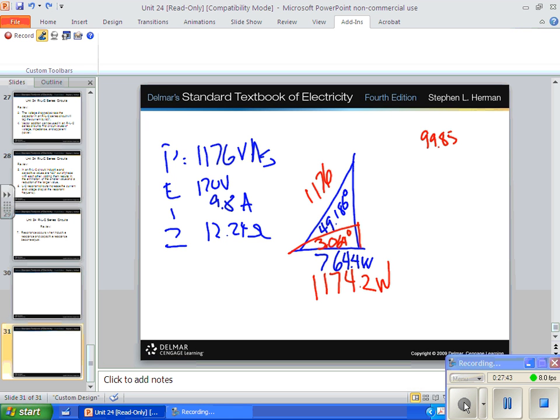But let's say that we only need to make 764 watts of actual power, because we designed this system with this particular motor in mind. But now we have it power factor corrected. Now, when it cranks that amount of power, it's going to draw less current, doing the same work, saving us lots of money. We like that.